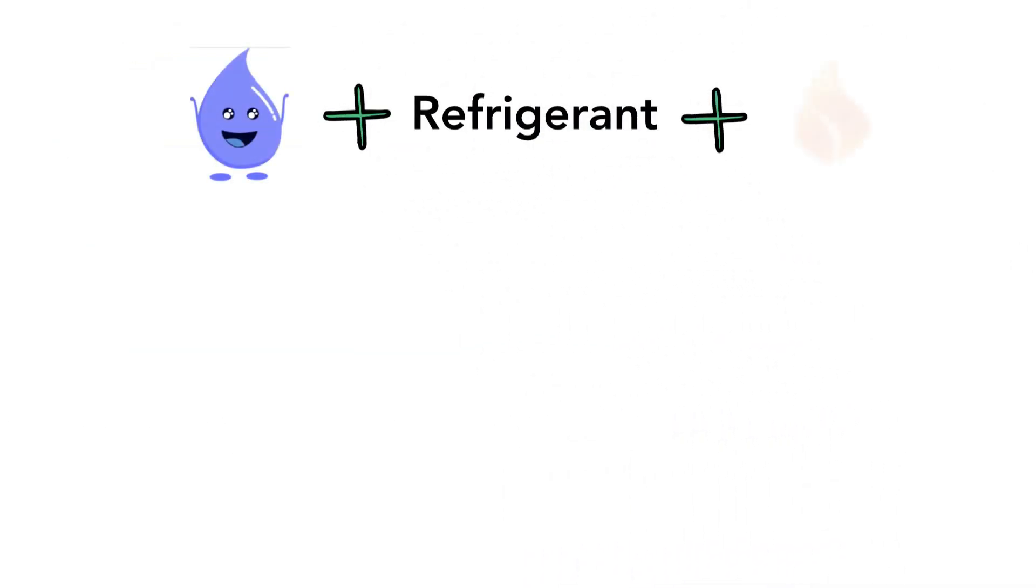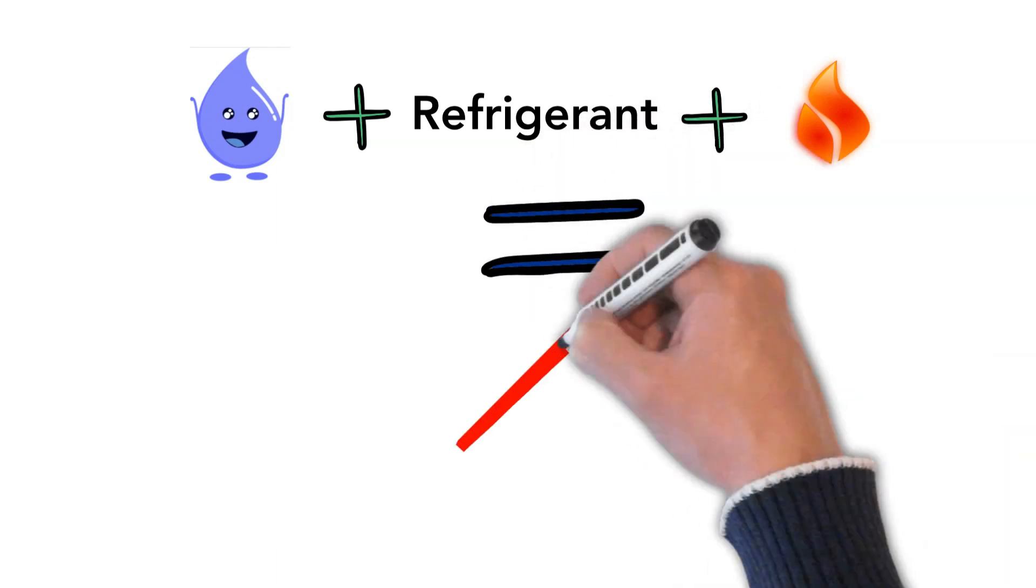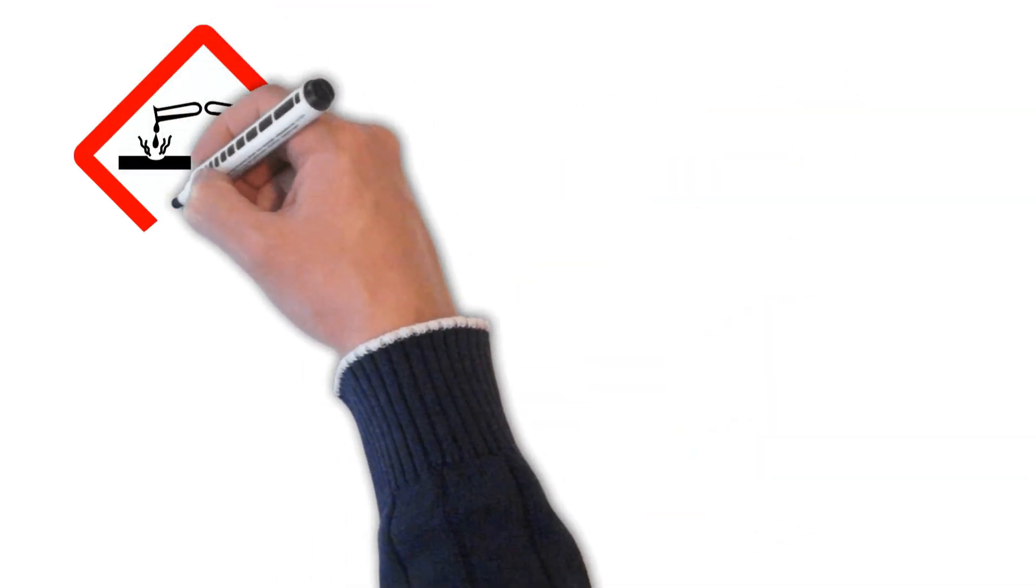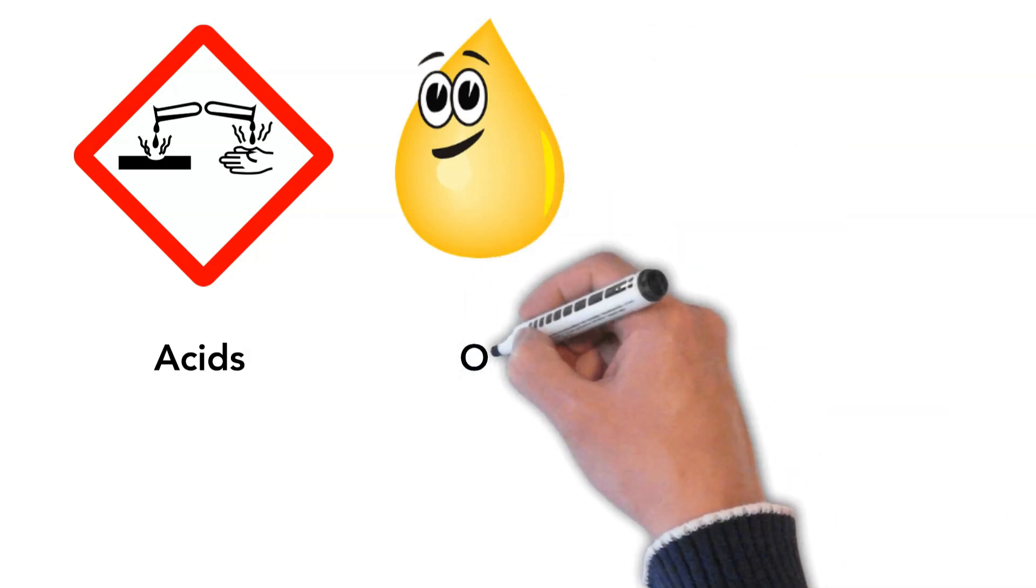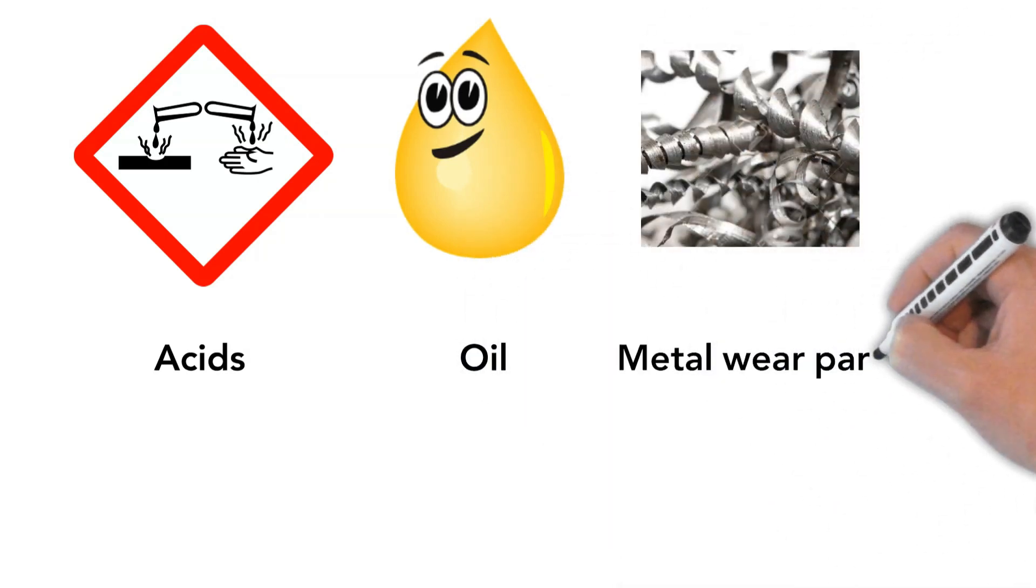Moisture, refrigerants, and heat can also combine to form acids. These acids mix with the oil and metal wear particles, leading to the formation of sludge.